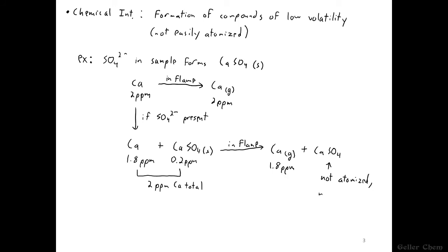Thus, not measured. Signal goes down. Signal lowered. Our sample might be 2 ppm calcium, but we're only measuring 1.8 of those ppms.